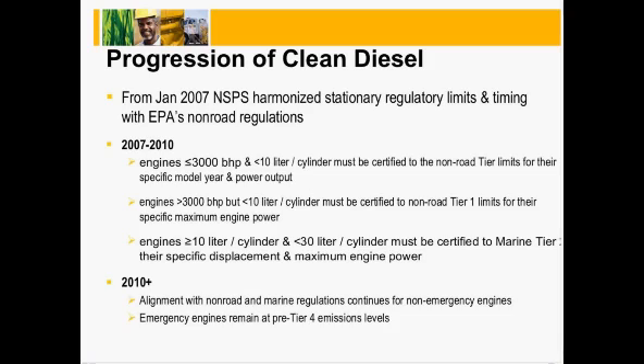the smaller engines in the less than 3,000 brake horsepower and less than 10 liter per cylinder were required to meet the non-road tier limits for the specific model year and power output of that engine, which is for the smaller engines, the Tier 3, the larger engines, Tier 2 outputs. But for the engines with a total brake horsepower greater than 3,000 bhp but less than 10 liters per cylinder, could still meet the non-road Tier 1 limits. For the much larger engines greater than 10 liters per cylinder, those would meet the marine tier limits specified for their displacement and maximum engine power.